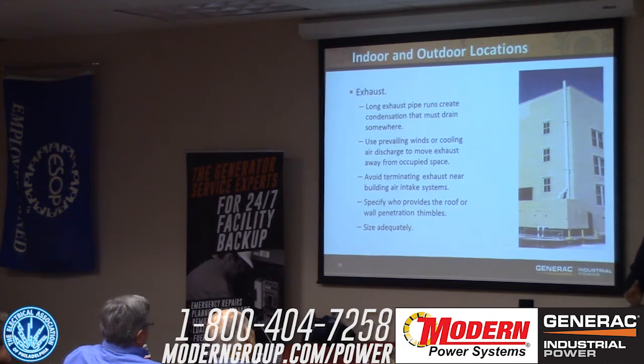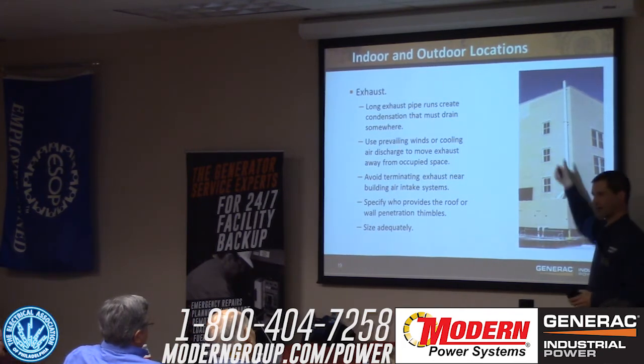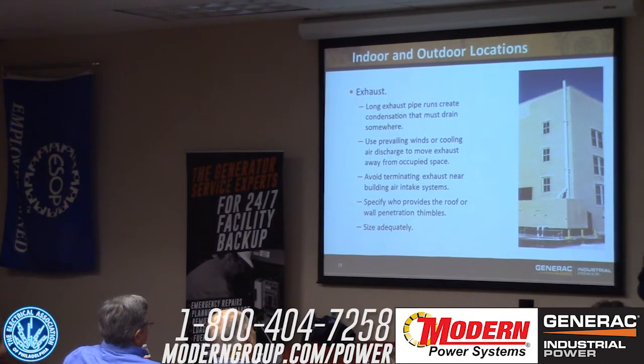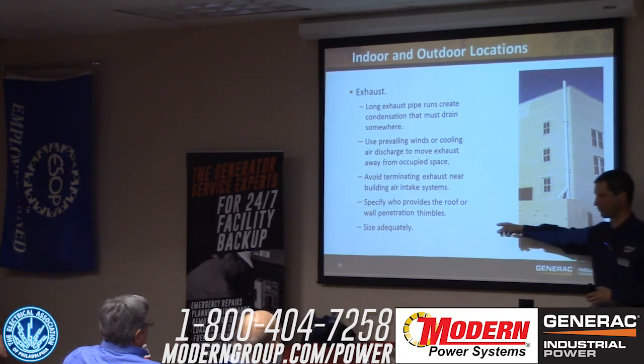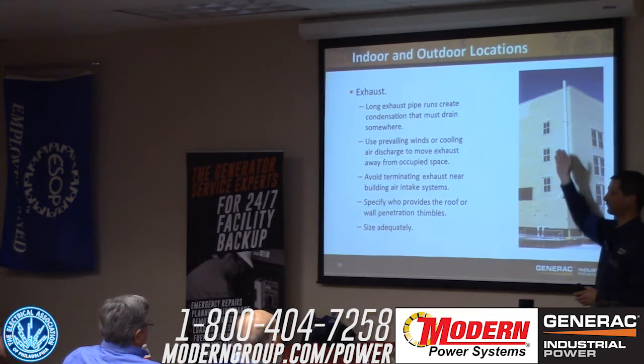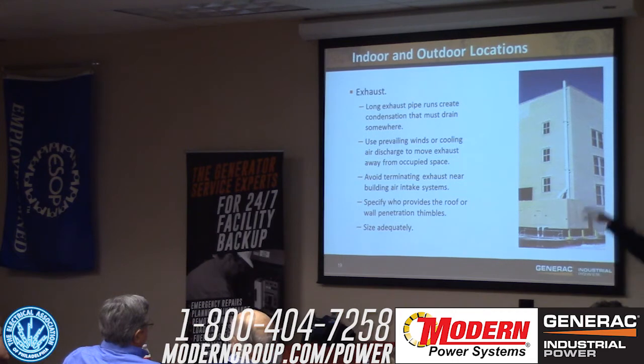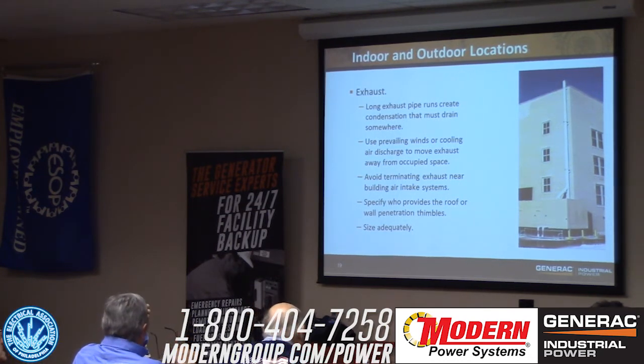The only way that engine is going to make horsepower is if I can get that exhaust gas out of there effectively. The sizing tools that I mentioned earlier will help with that. If you've got a 50-foot vertical exhaust stack with, let's say, two 90s in it, it's going to tell you what diameter that pipe needs to be so that you don't exceed the maximum back pressure on the engine.